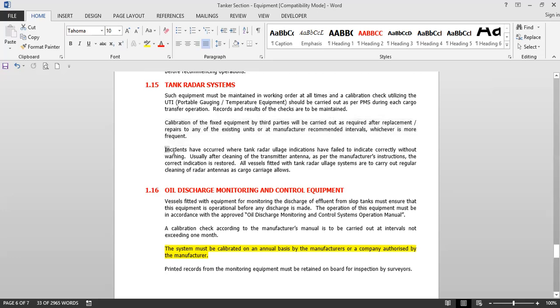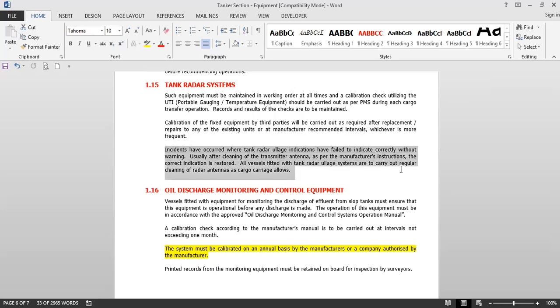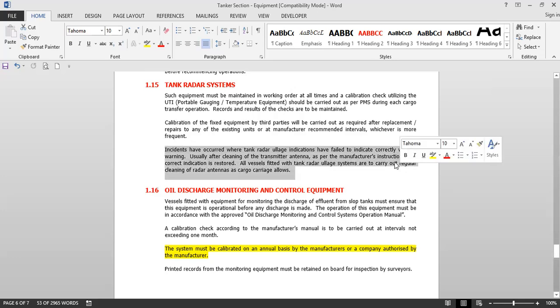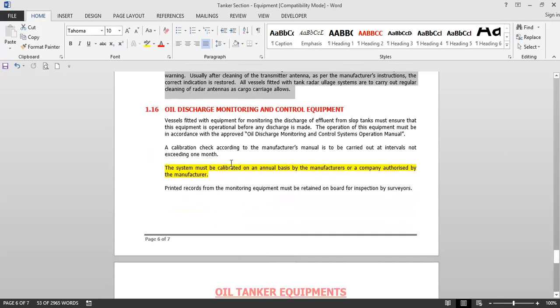Incidents have occurred where tank radar indication systems failed to indicate correctly without warning, usually due to dirty transmitter antennas. As per the manufacturer's instructions, cleaning of the antenna restores correct indication. All vessels fitted with tank radar systems are to carry out regular cleaning of the radar antennas as cargo carriage allows — during every ballast voyage the antenna must be opened and cleaned. If even after cleaning it is not giving correct readings, a service technician should be called to repair it.